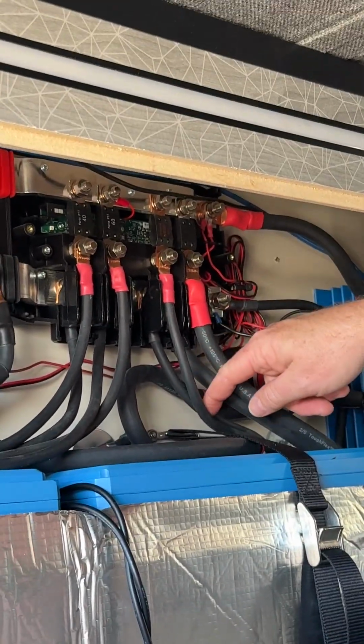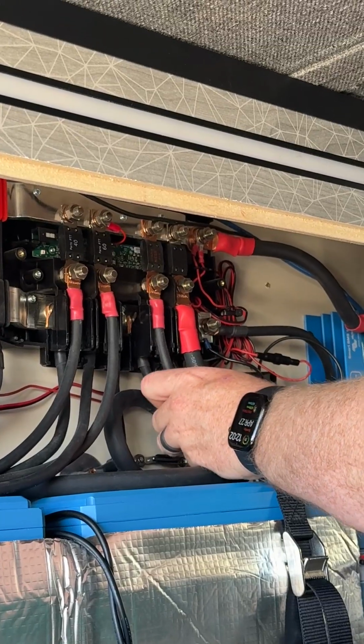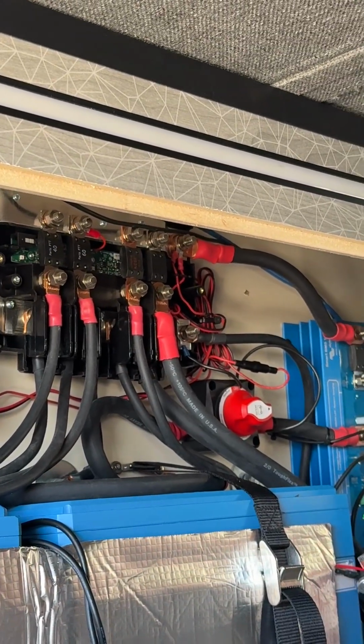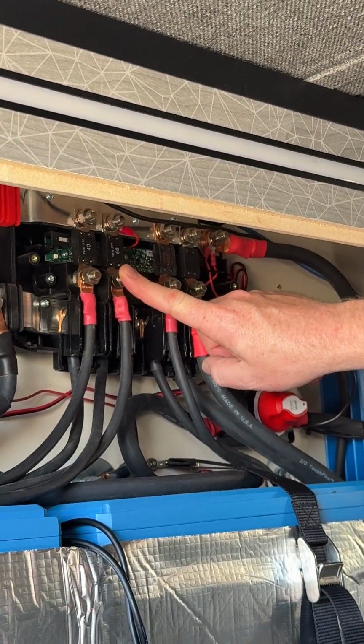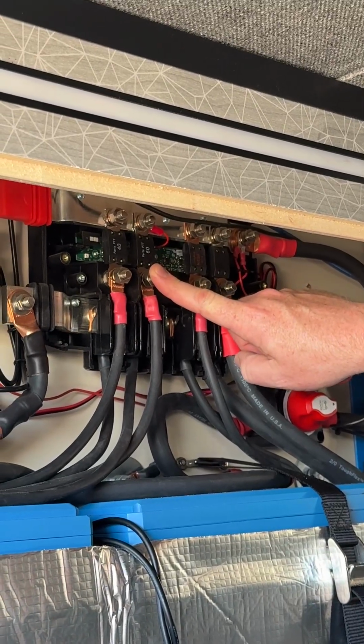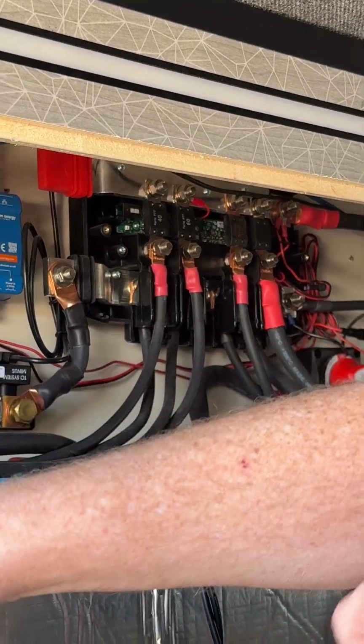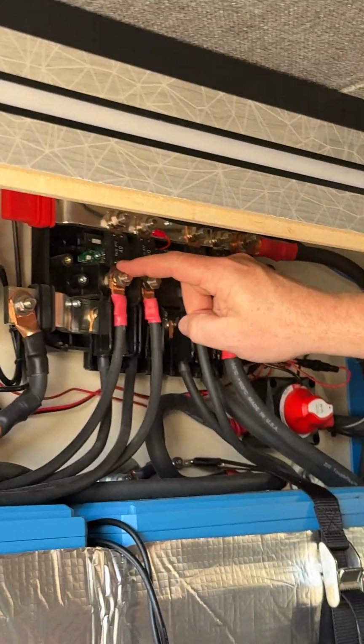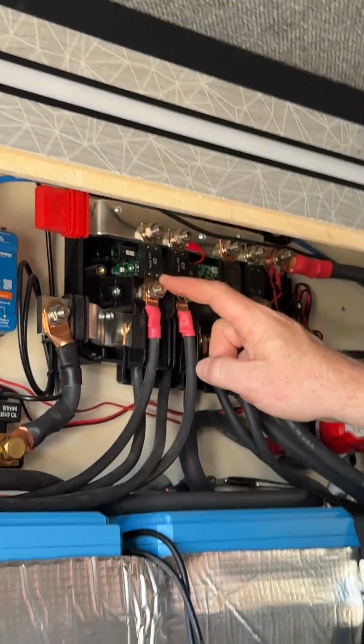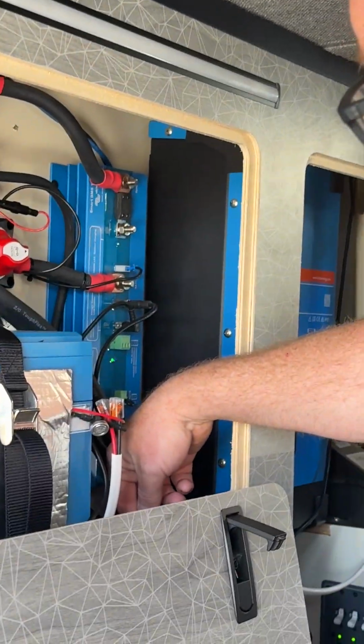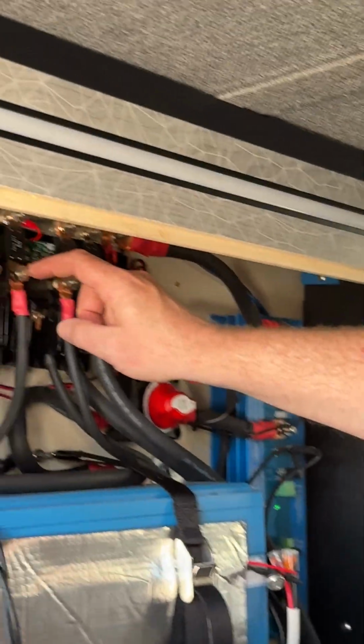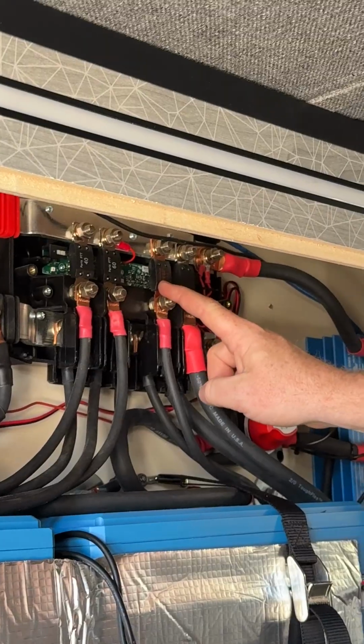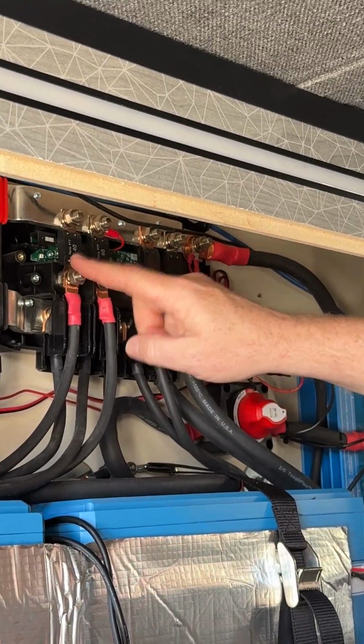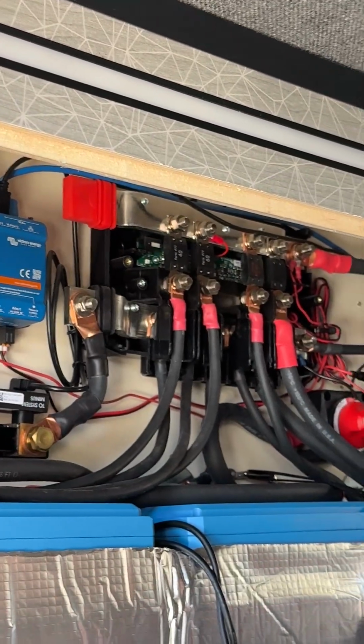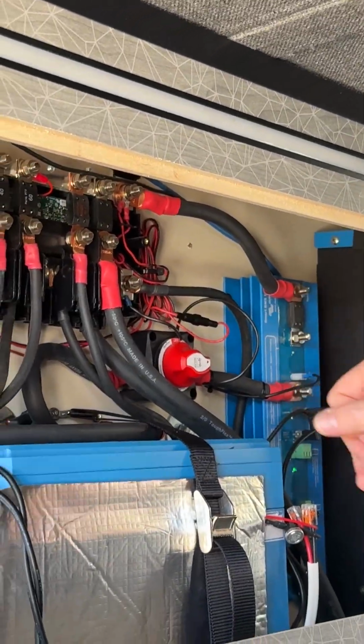What's the 80 ampere here? That's our main fuse panel, just like the low voltage circuits. We have our 60 that goes to our secondary panel back here for our exterior lights, and then our solar controller coming into here. There's a little fuse panel down here for all the exterior lighting systems, a fuse panel here for all our normal low voltage circuits, and then inverter and solar back here. So solar input, because the Orion comes through this, which just charges directly to the batteries.